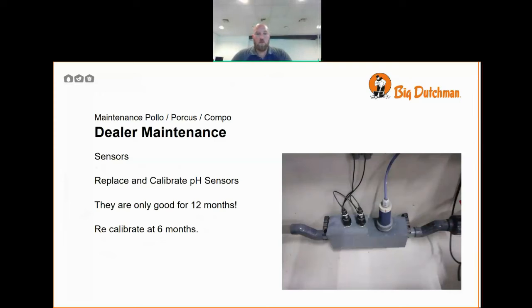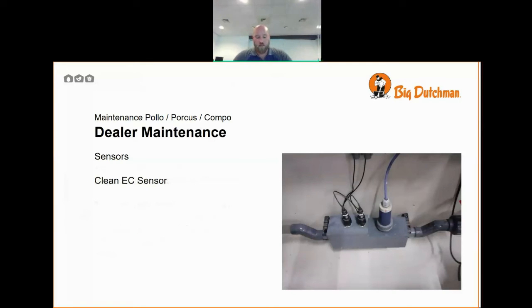pH sensors. Replace the pH sensors every 12 months. And these will need to be recalibrated when new, but also at 6 months. So if you're going to a client every 6 months, you want to recalibrate the first time, and then the second time replace and recalibrate.